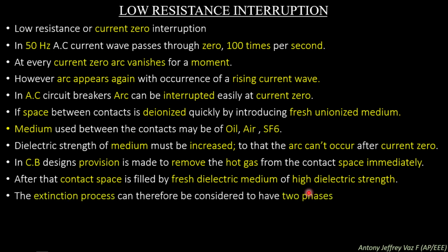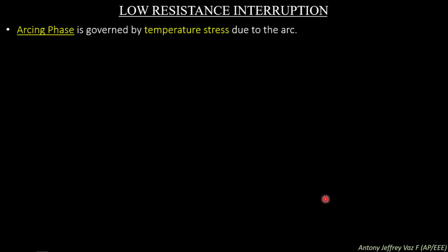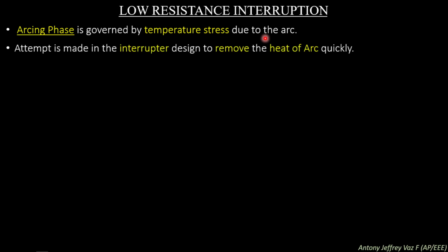The extinction process can therefore be considered to have two phases. One is the arcing phase. Second is the post-arc phase. The arcing phase is governed by temperature stress due to the arc. An attempt is made in the interrupter design to remove the heat of the arc quickly.